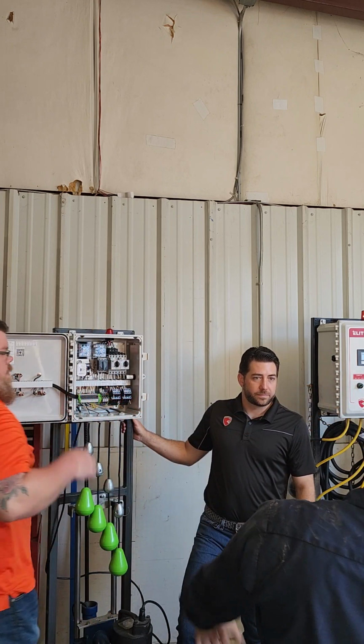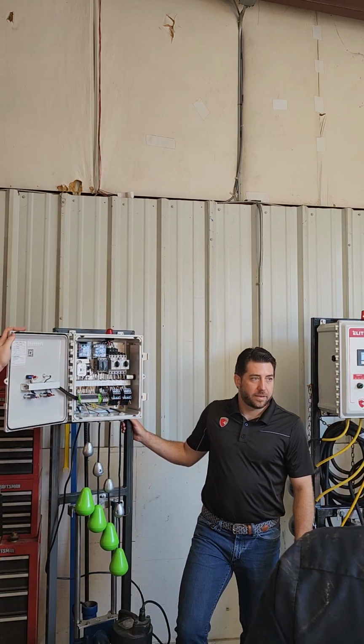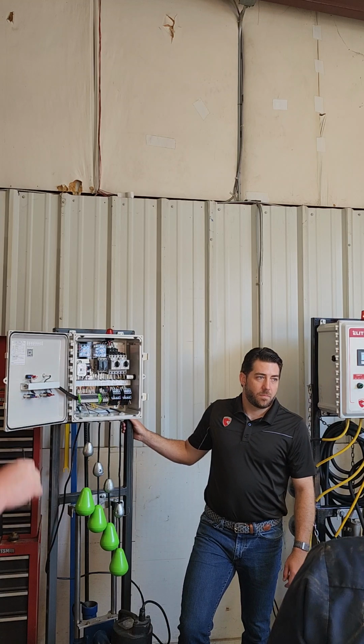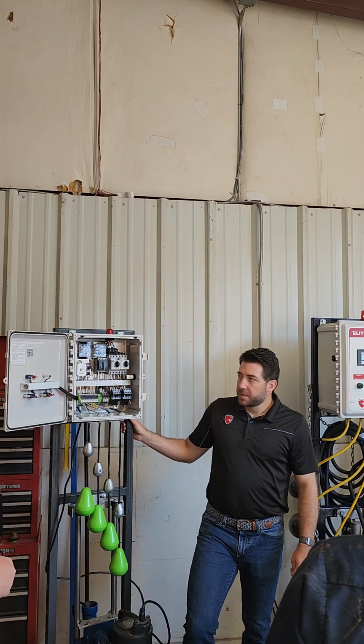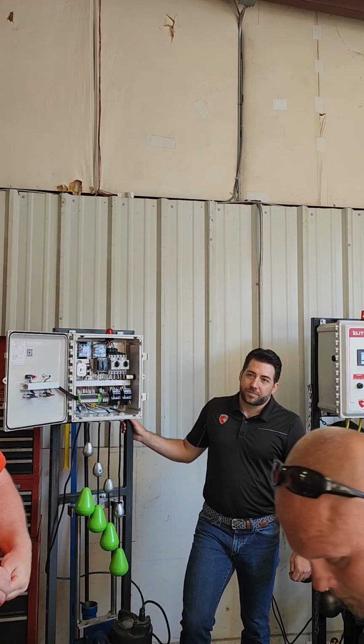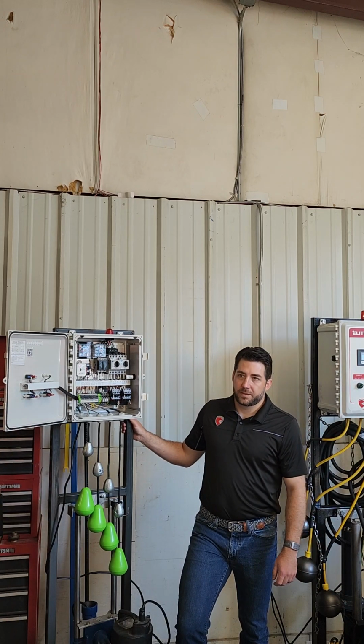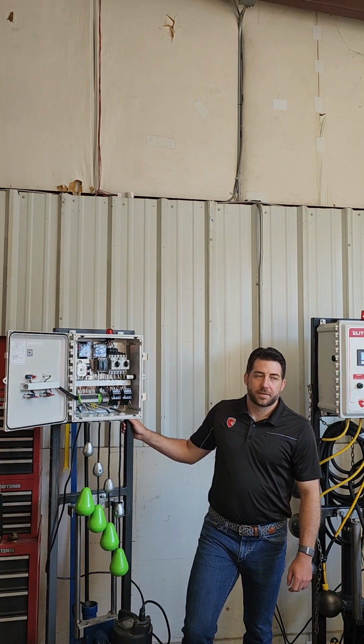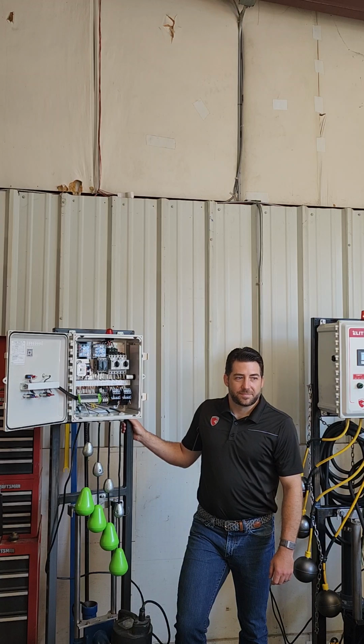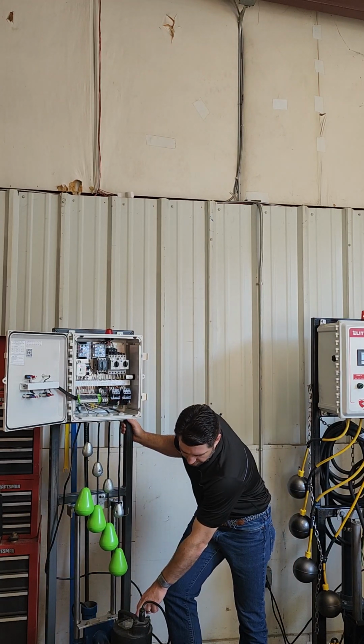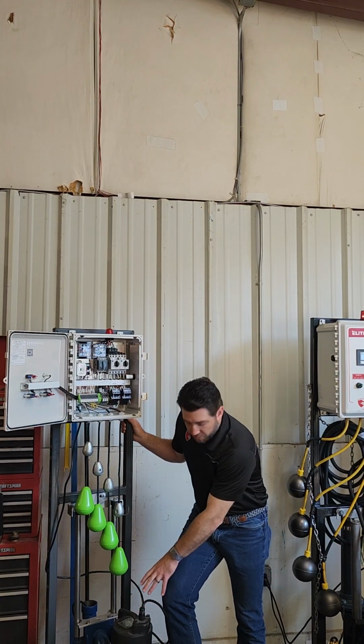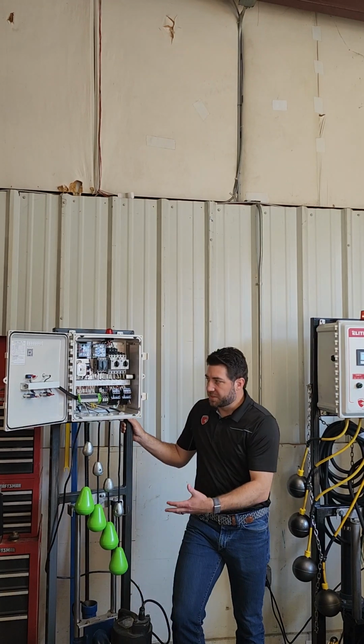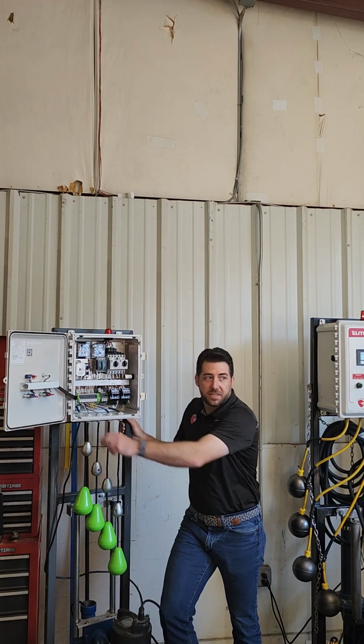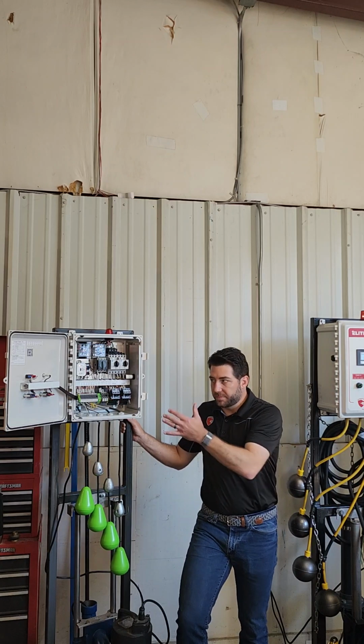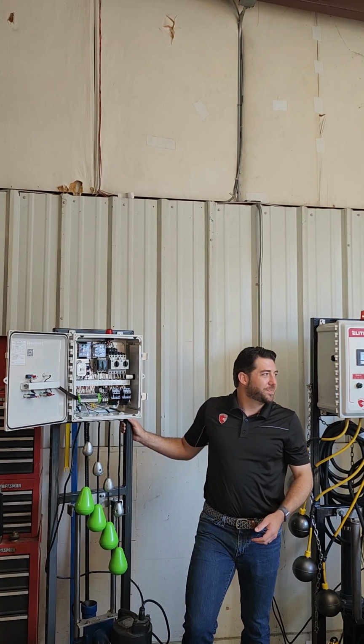Let's say that we're inspecting one and it wasn't the right one. What would that cause the pump to do? Great question. Well, let's say if it's lower than your amps. So say you're 12.6 there, but you're not 12.6 there. How would you know just off the bat? Sometimes when you buy these pumps, they come with a sticker and you can put it on the inside of the door and you can see what it's supposed to be, if that's the same as what's in that pump.